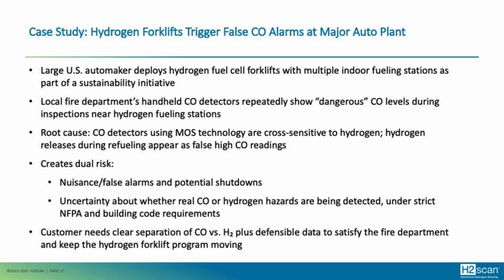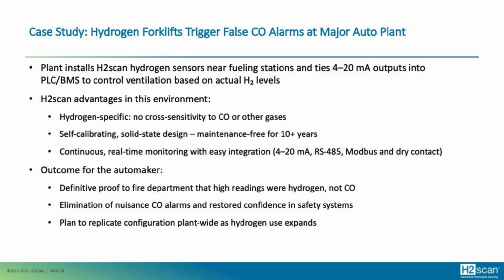And so they were using a technology that was cross-sensitive to hydrogen, which is very common. You won't necessarily find a lot of CO detectors that can separate CO from hydrogen. So as a result, they installed our hydrogen sensors, which are hydrogen specific. And so now they know if it's CO or hydrogen that they're seeing. And they connected it to their building system, which ramps up fans based on the hydrogen level. So that was a very good example of how nuisance alarms or false alarms can create a lot of havoc inside a facility. And so knowing what you're sensing is important, especially if your detector can sense multiple gases. So this was a good outcome for this situation.